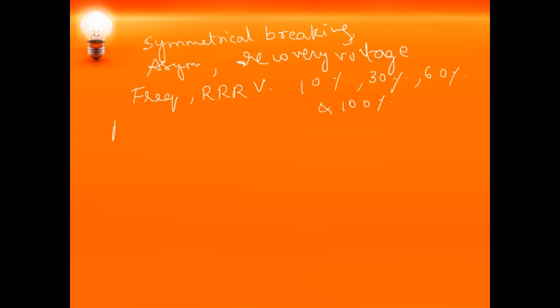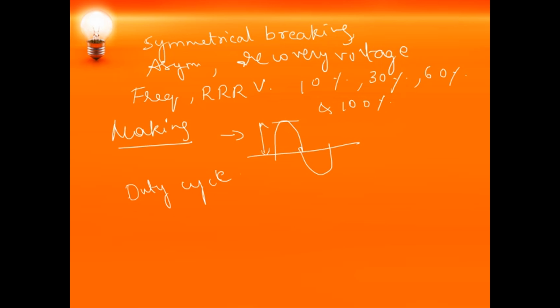Next is the test for making capacity. Making capacity means the master circuit breaker and the circuit breaker under test will be closed first. After that, short circuit current is made to flow. The peak value of the short circuit current will be noted. Next, coming to the duty cycle test. The duty cycle test will be performed like this: breaking, after 3 seconds again breaking, after 3 seconds again breaking. It will be conducted for 10%, 30% and 60% of the rated symmetrical breaking capacity.